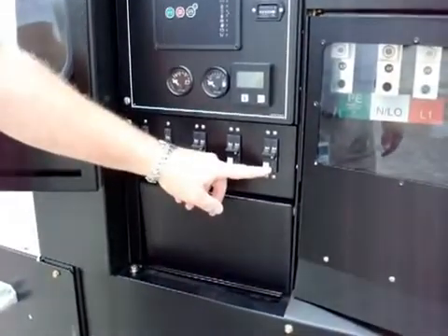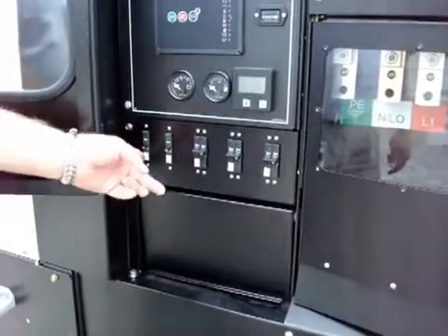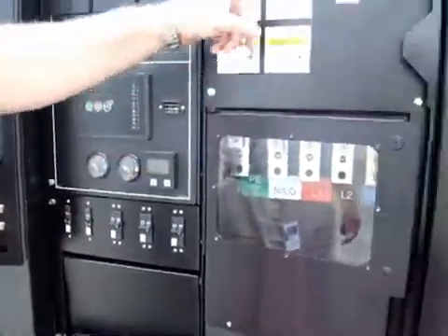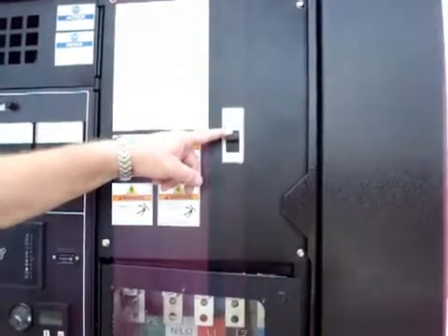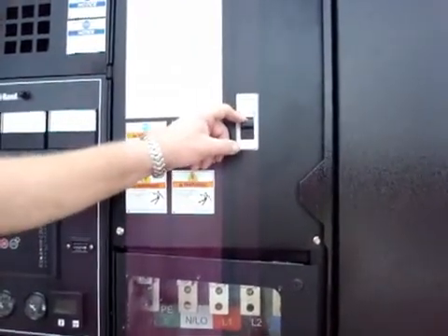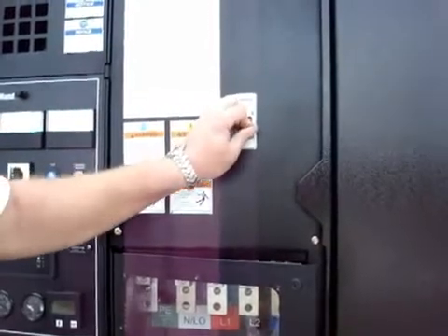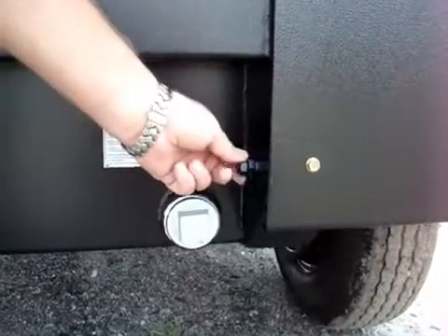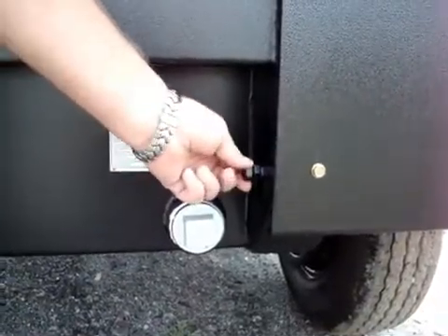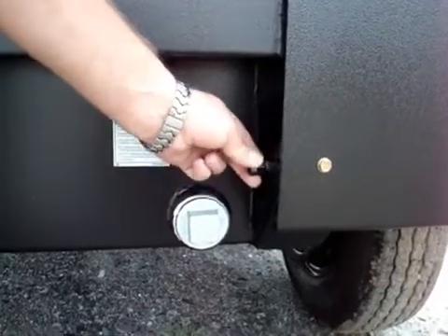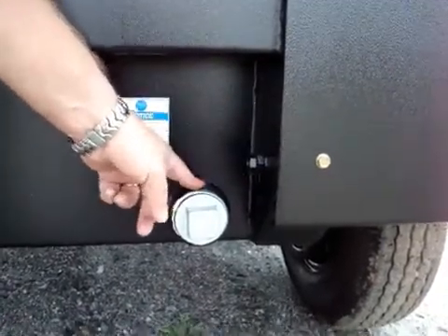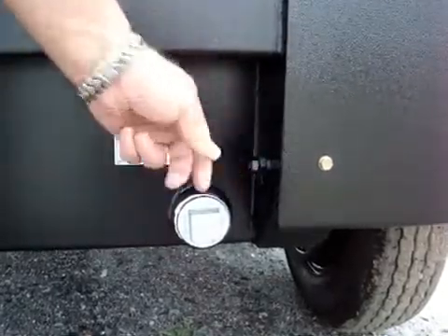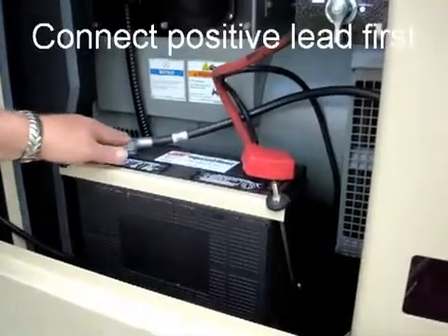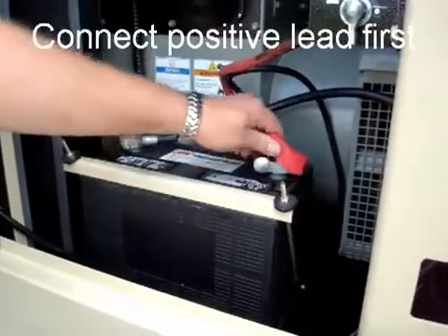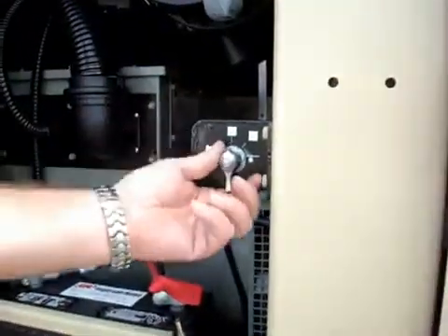Each receptacle has its own individual circuit breaker for overcurrent protection, along with the main output breaker from the generator. Prior to startup, we want to verify that this circuit breaker is in the open position. Additionally, if grounding is required by local codes, we have a chassis ground connection located down here right above the containment drain plug. After verifying that our cables are connected and tight in the proper sequence, we'll shut our battery disconnect switch.